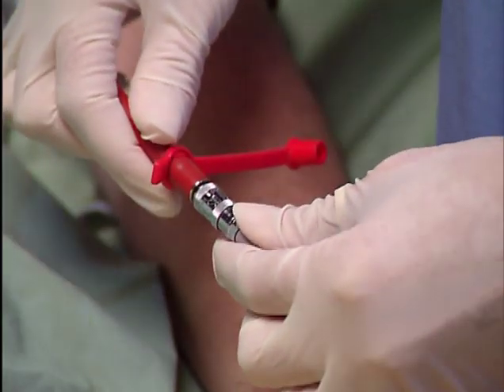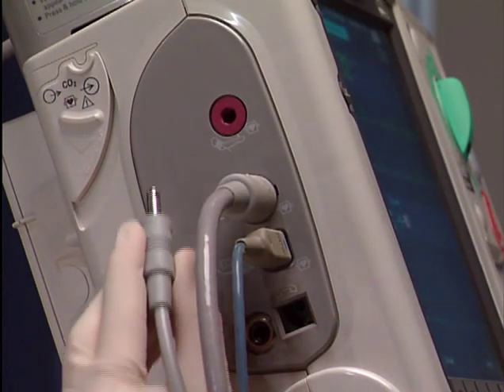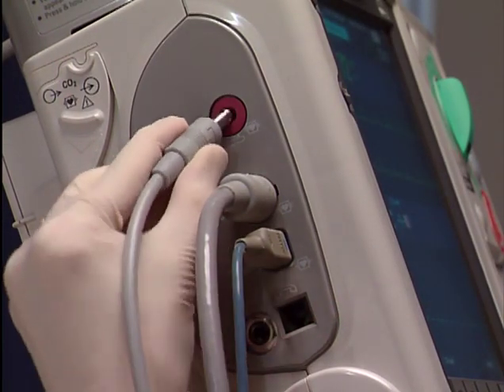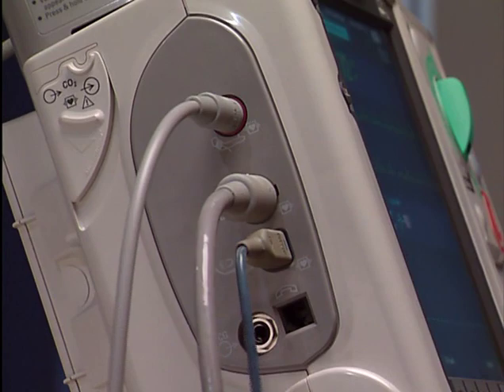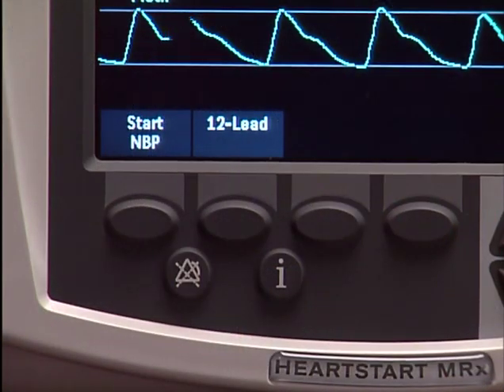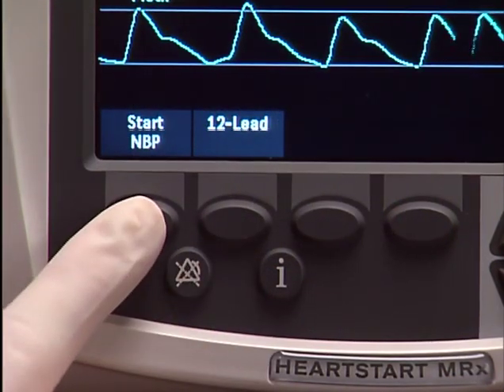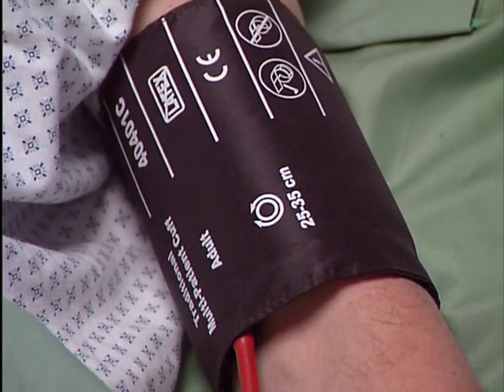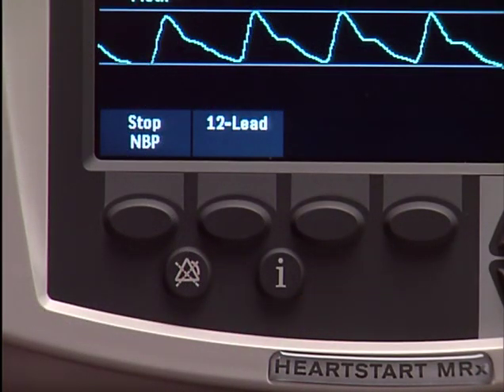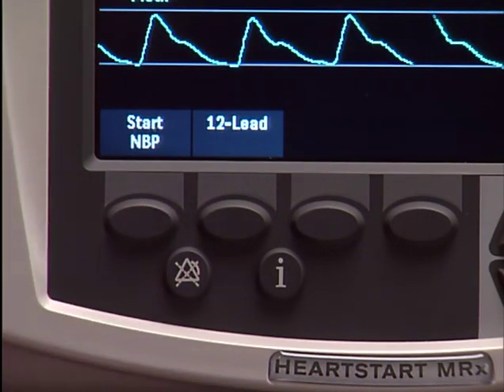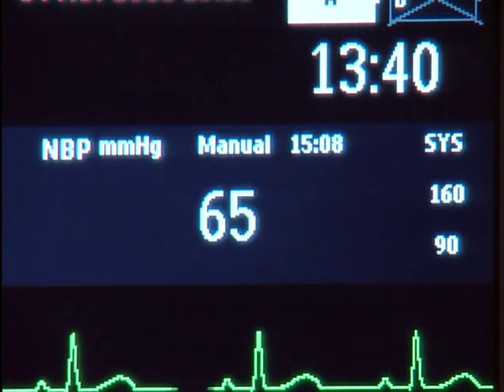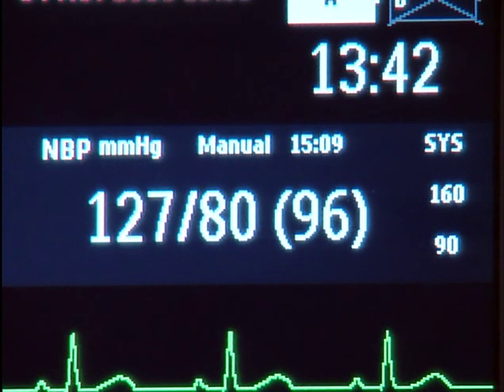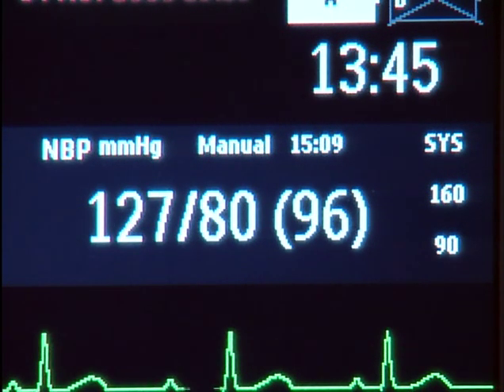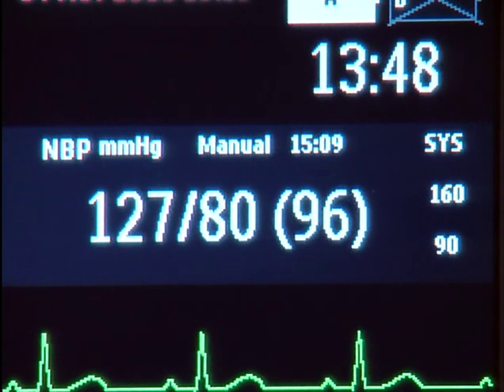Attach the cuff to the tubing and the tubing to the NBP port on the measurement connector module. To perform an NBP measurement, press the Start NBP soft key. The cuff inflates and then slowly deflates. If you need to stop the NBP reading, press the Stop NBP soft key. The NBP measurement appears on the screen as systolic followed by diastolic with the mean arterial pressure in parentheses.